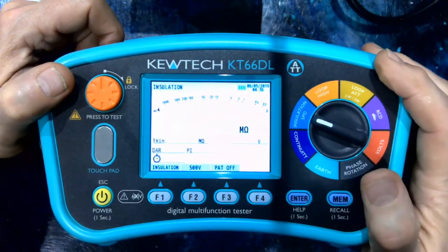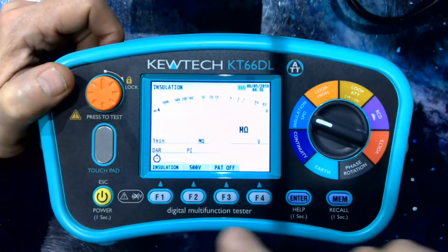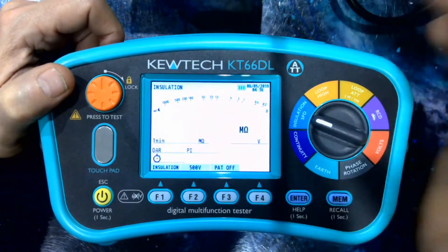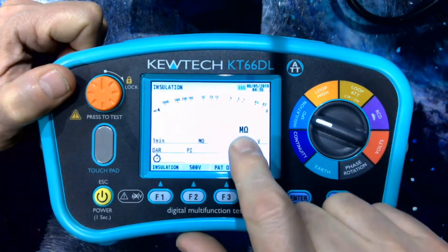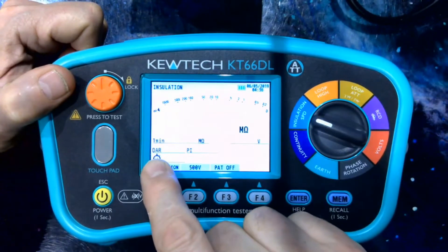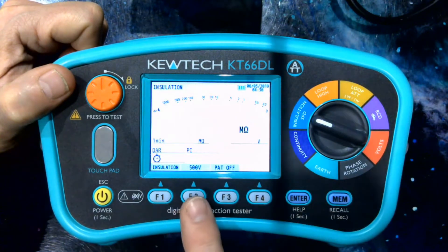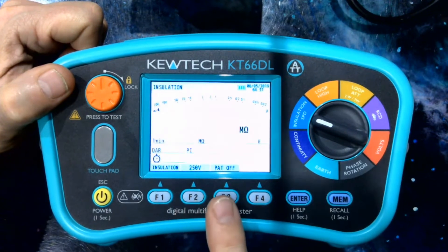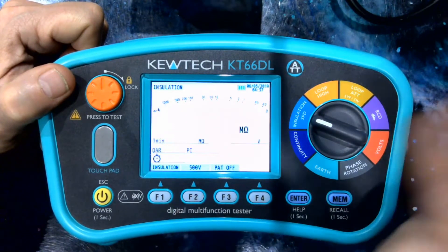Moving on to insulation — here we can see the benefit of the dot matrix screen. It gives you a digital bar graph of how the insulation is testing. Test results come here and you also have the opportunity to do a DAR and your polarization index. We have a range from 100, 250, 500, and 1000V. For PAT testing you've only got 250 and 500 in line with the standard.